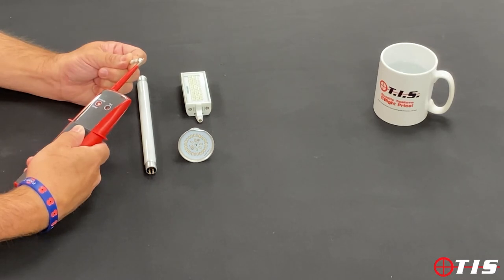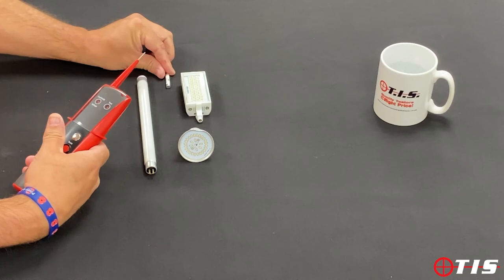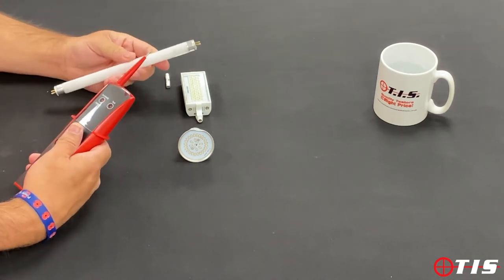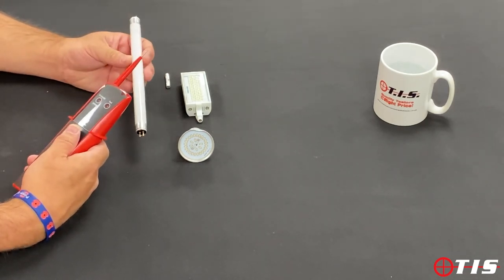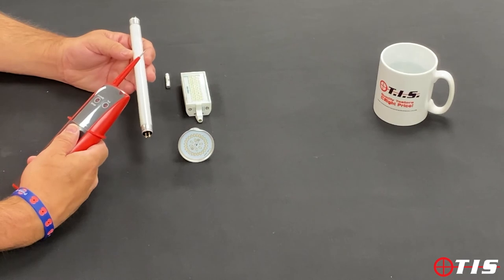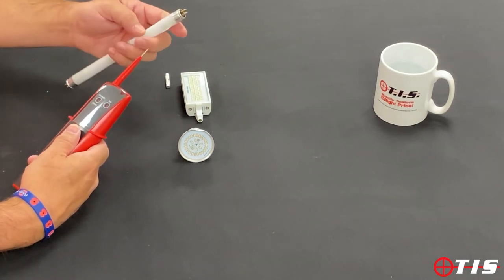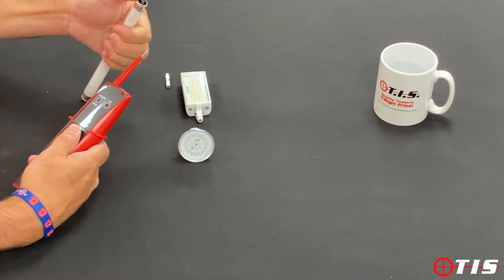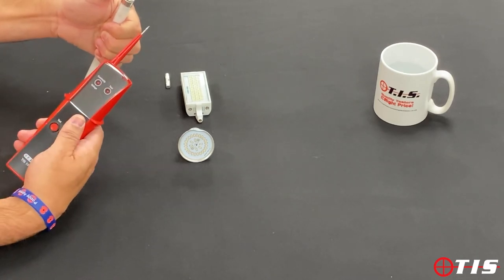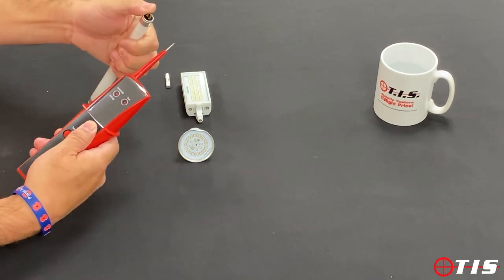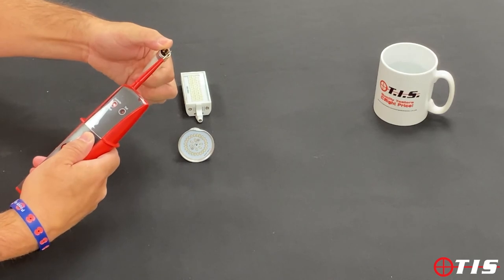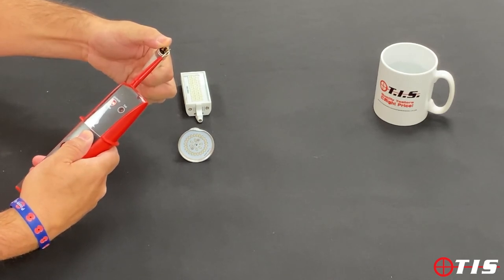When it comes to a tube—we've got an 8 watt tube here—it will test an 8 foot, 6 foot, or 5 foot tube; the size doesn't matter. There are two tests to do. First, put your thumb on the silver plate on the tester and the probe on the other end of the pin. This tells us the ignition on that side is good.